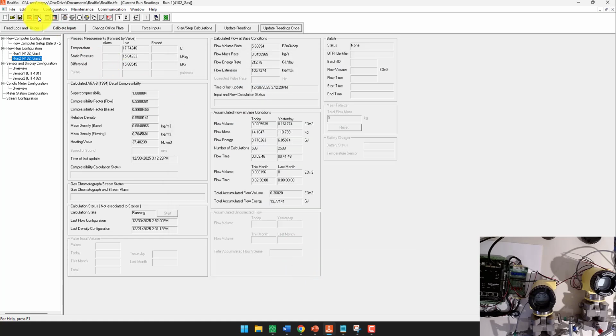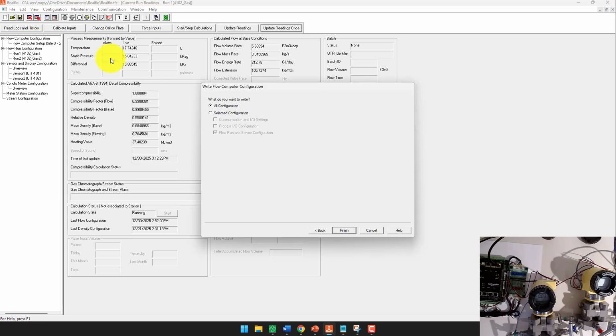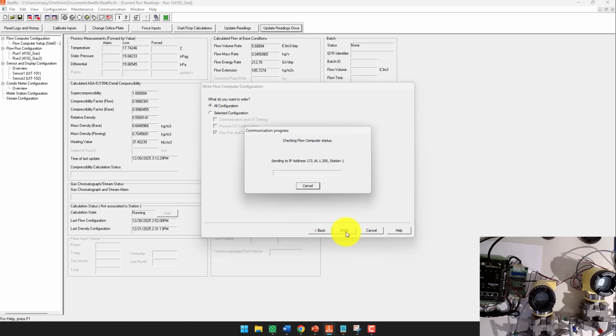We'll hit OK. We'll go ahead and write this config. And we could hit all config. For the SCADAPack 575, these both do the same thing. On older SCADAPacks, you could write a bunch of other information to the SCADAPack, so you'd always want to just write the flow run and sensor config. But on the newer SCADAPack, the X70s, you could hit either of these. It's the same thing. So we just hit yes here. It's just saying that the flow run's currently running, so we want to write the config.